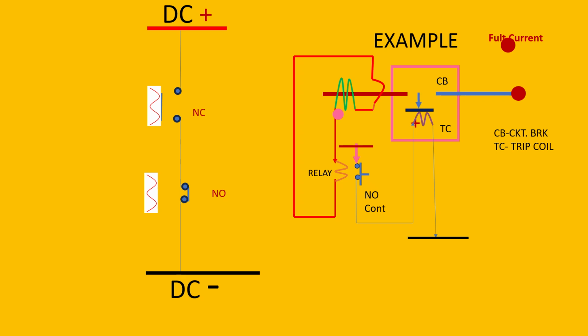Friends, for an example of the use of this contact, I'll show you how a normally open contact, when it makes, extends the DC positive and trips a circuit breaker. So here in the picture, what we are doing is, against a relay normally open contact, in one contact we are giving DC positive, and in the circuit breaker trip coil, which has been shown in green color, the negative is permanently given.